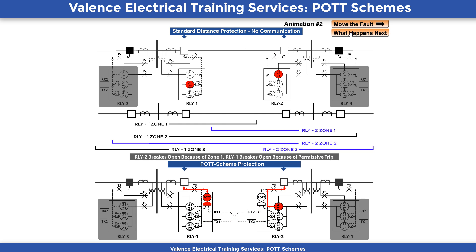Relay 1 should trip in 20 to 40 cycles in the normal protection scheme because it has detected a Zone 2 fault, which means the fault could be on the line the relay is supposed to protect, or it could be on the line Relay 4 is installed to protect. Therefore, it's going to wait for Relay 4 to trip in case the fault is on Relay 4's line. The POTT scheme on the bottom of the screen will not wait, because it's getting feedback from Relay 2 that the fault is on the line. If Relay 1 and Relay 2 both detect a Zone 2 fault, that means the fault should be in the overlapping region between the two relays, which is between 75 to 100% of the line. Relay 1 will trip after a short communication time delay and remove the fault from the system.